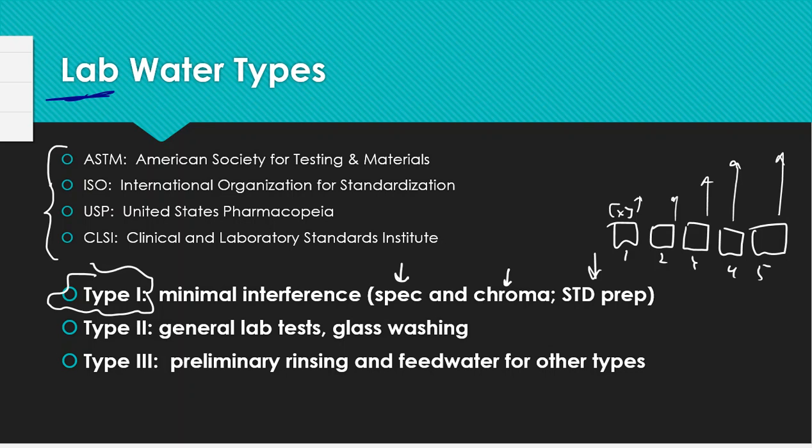So type 1 water, that's what this whole arena is going to take place with. Type 2 water, this is great. The restrictions here are not as tight, and the reason is that this particular type of water is just for general laboratory testing. General use water in a laboratory environment that's not going to go to analytical instrumentation, that's great for type 2 water. I'm not going to have an instrument that's going to interfere with really tiny contamination amounts. And for everything from glassware washing, type 2 water is typically going to be okay.